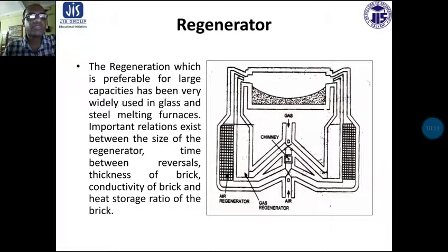Accumulation of dust and slagging on the surface reduces the efficiency of heat transfer as the furnace becomes old. Heat loss from the walls of the regenerator, and air in-leaks during the gas period and out-leaks during the air period, also reduce the heat transfer.